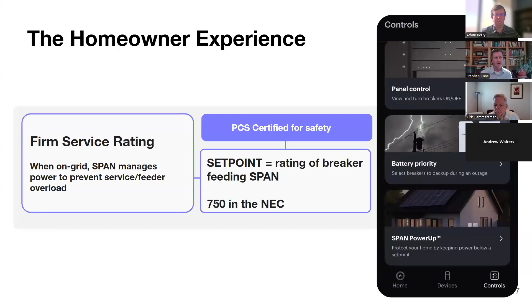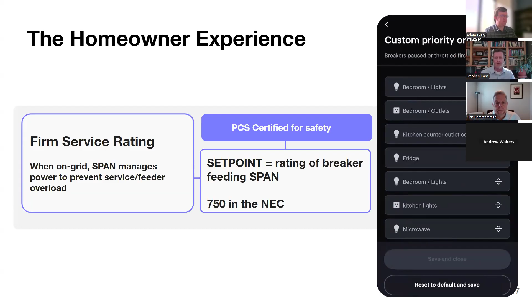As far as the homeowner experience, we do have to consider there's probably an upper limit to what occupying a home that is energy managed feels like from a good homeowner experience. And again, we've got the firm service rating that gets set in the settings by the electrician. But the homeowner should have some agency over what's being curtailed when. And so we do see some applications where they can change the rank order of what's getting curtailed. But I would say that 90% of the time, you pause the EV charger for just a few minutes, you can ride out these high power events, and a homeowner won't even notice a brief pause in their EV charging, or even a curtailed or dynamically ramped down amount of current to their EV charging.